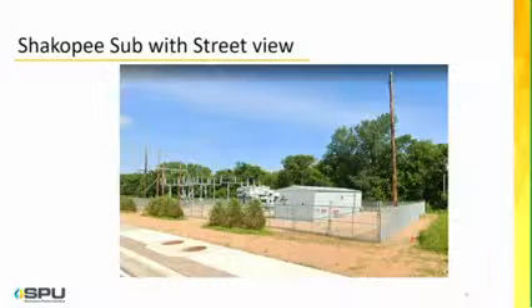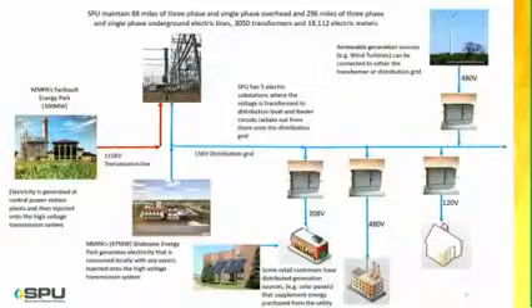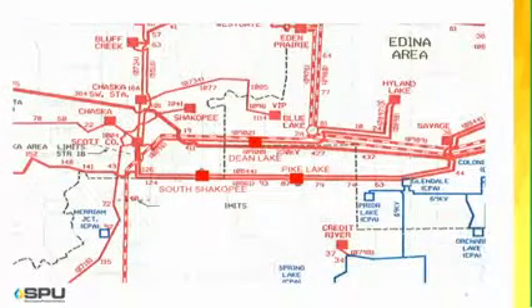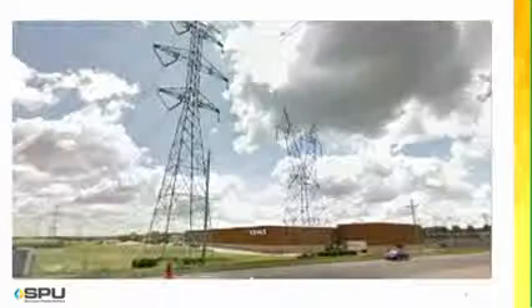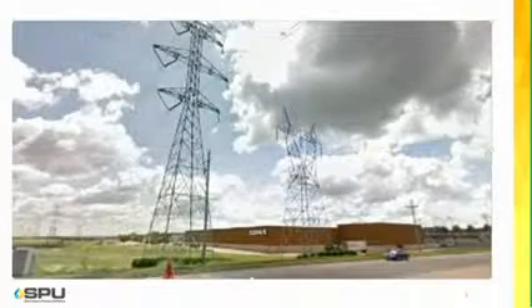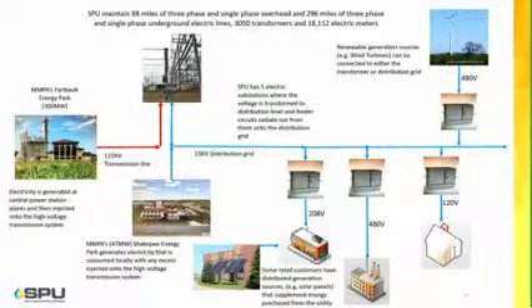You might just be able to make out there's a circuit breaker just by that central bush or shrubs out front. That's a 115 kV breaker. Going backwards, you can see where it says Shakopee. That's still the location, right next door where the original Shakopee sub was. The red line tracing back to the Scott County sub is at 69 kV, which is really a sub-transmission voltage since it's under 100 kV. But that is how that substation is fed.